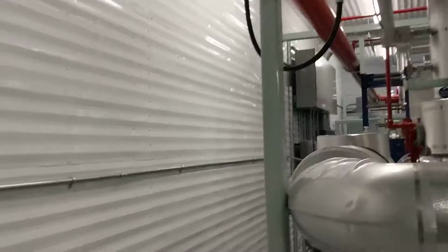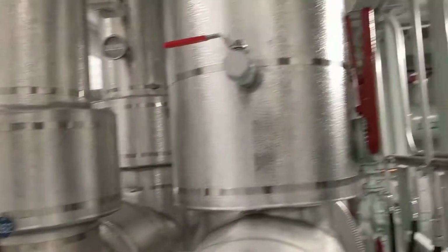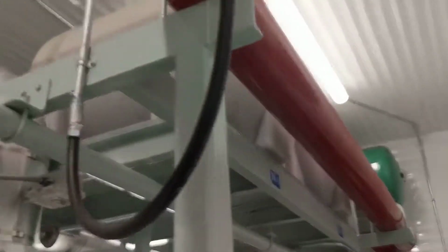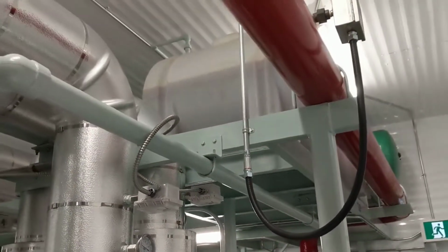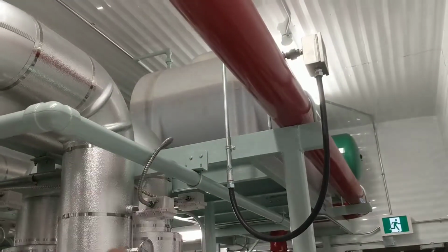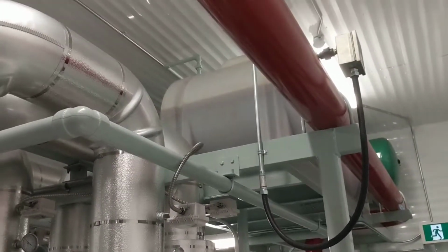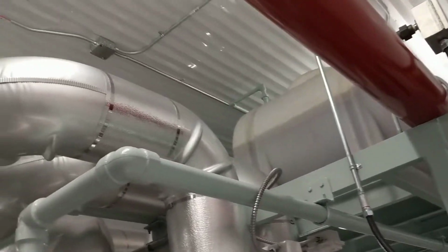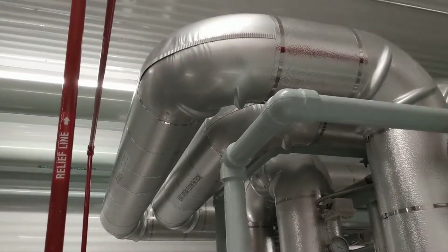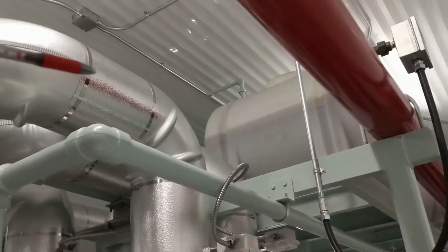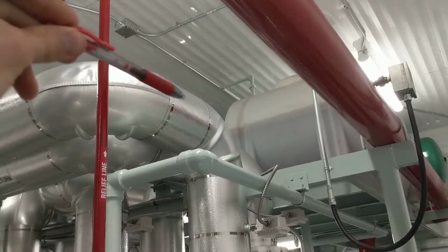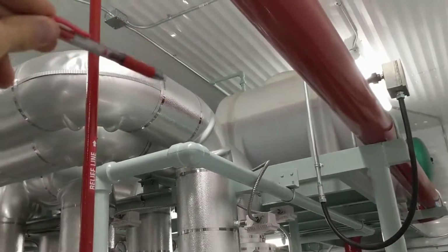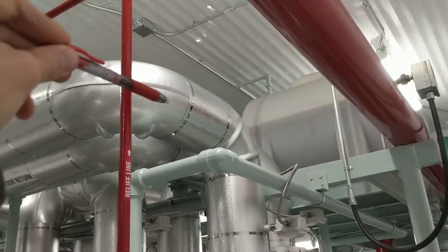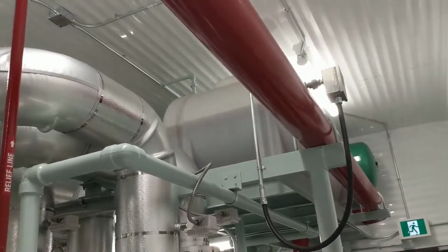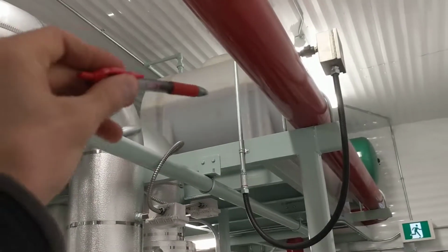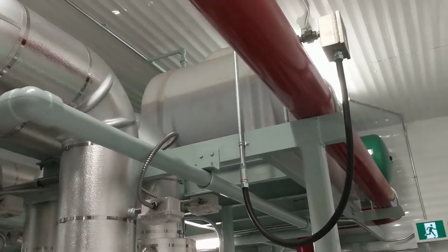On the balance tanks, it's important to maintain a higher level than you might otherwise think. When you look at that balance tank up there, it looks more than half full, like it's got lots of brine in it. But if you look at how high the top of these lines are, these lines sit up quite high relative to the balance tanks. So if your balance tank's too low, you could be down below the level of these lines and think that you're still okay. So we're going to mark what the safe line is on those tanks.